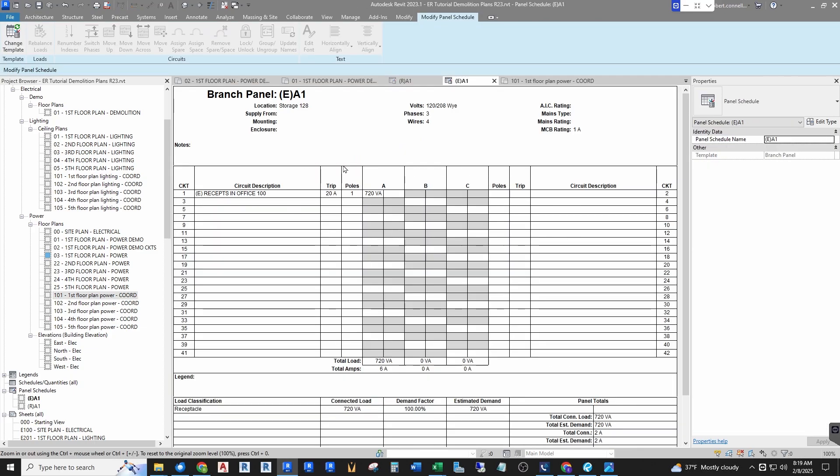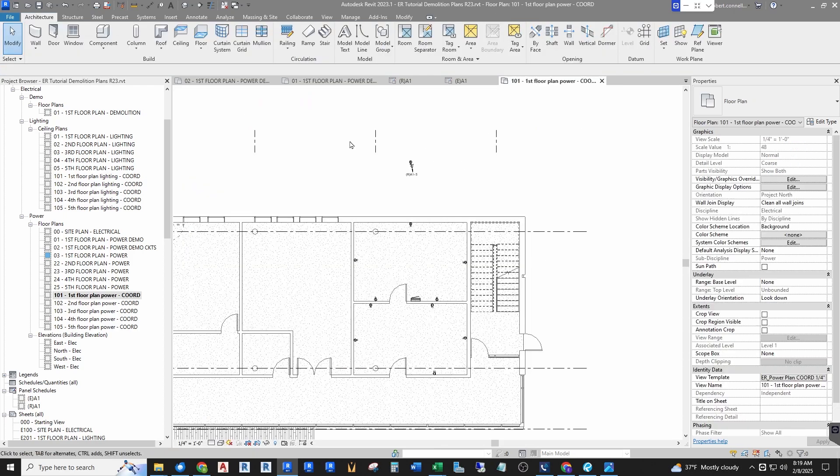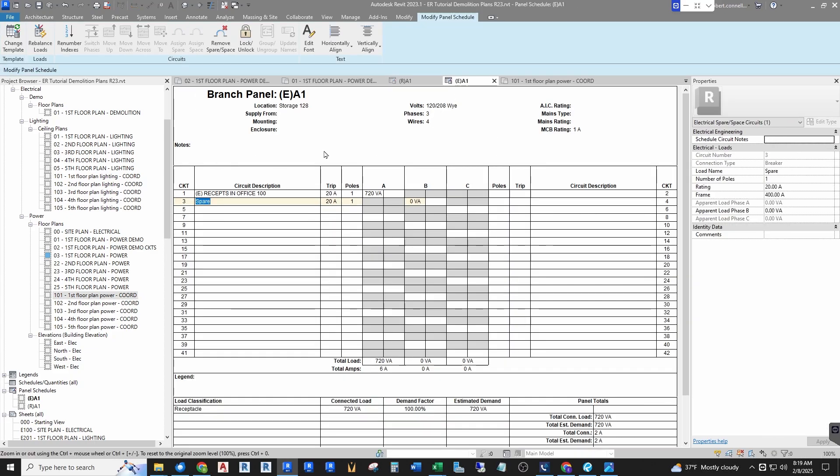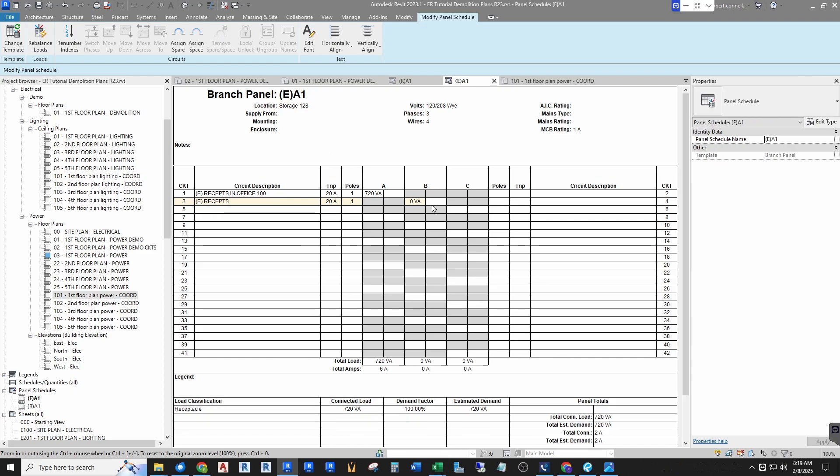Now this old panel, this is a demoed circuit I can leave that there. If I want to show other demoed circuits I could create them as separate circuits like I just did there. I could create all these existing circuits here to show for demo, or I can merely put a spare breaker in here and just call it existing receptacles. And I don't worry about the load because it's an existing panel that I'm demoing. I don't need a tally of all the loads here. I just need a panel schedule.